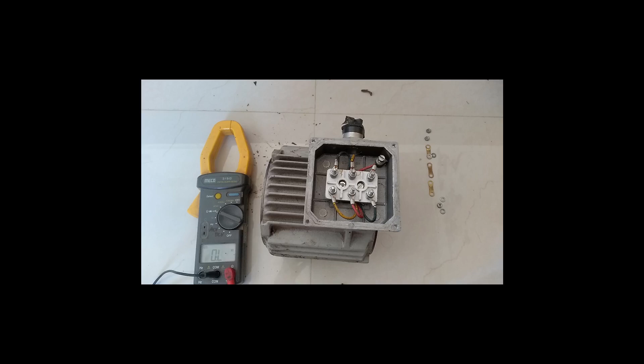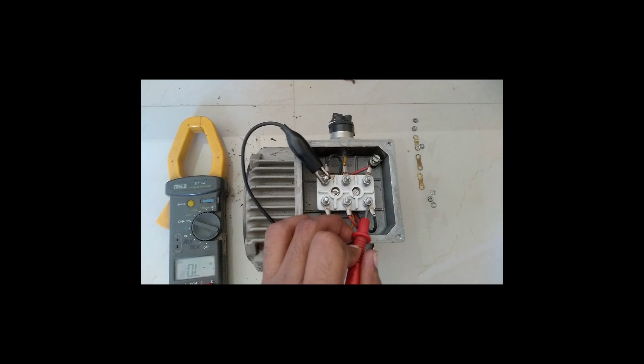So now let's check the winding of this motor using a multimeter. We have connected to one phase, which we considered as U1. Here you can see U1 and U2 is open circuited, it's showing overload, so this phase is open. Now let's check the next phase, V1 and V2. This phase is showing some resistance, but it's highly unstable. You can see the value is constantly changing, so this might be because of my hands also, but the value is not stable. So this V1 V2 phase has some resistance, some continuity in it, so this phase is almost intact.